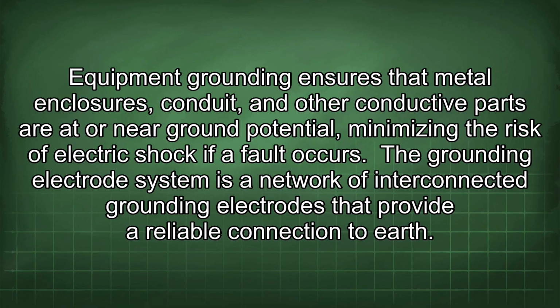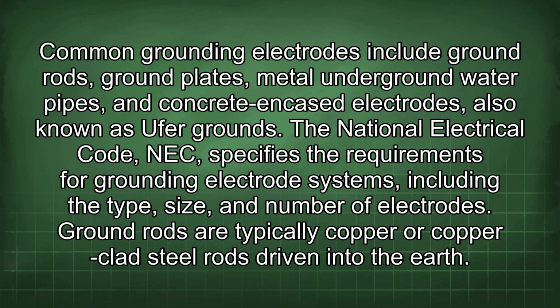The grounding electrode system is a network of interconnected grounding electrodes that provide a reliable connection to earth. Common grounding electrodes include ground rods, ground plates, metal underground water pipes, and concrete-encased electrodes, also known as UFER grounds. The National Electrical Code (NEC) specifies the requirements for grounding electrode systems, including the type, size, and number of electrodes.